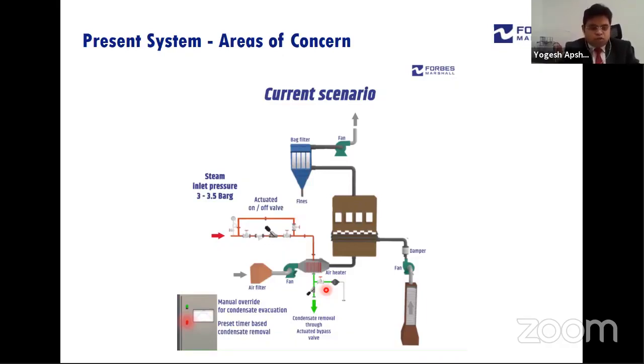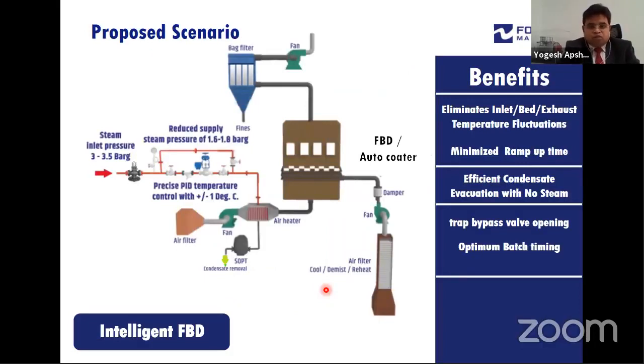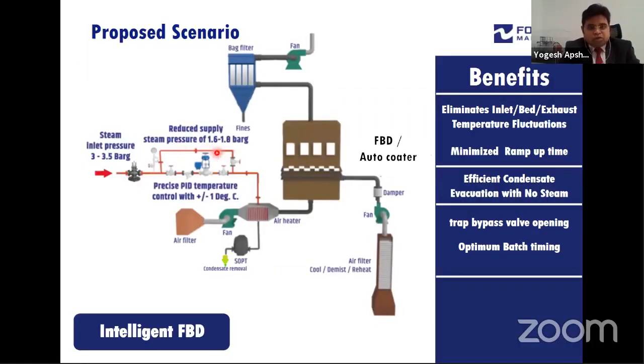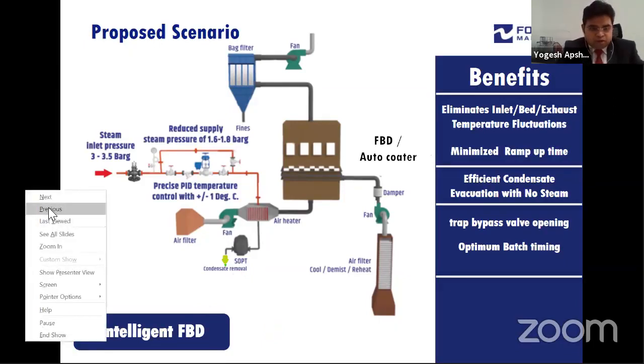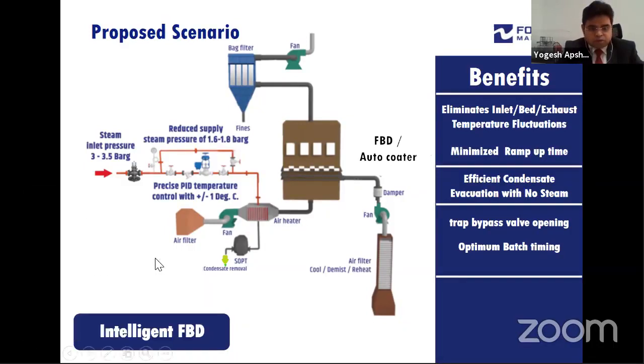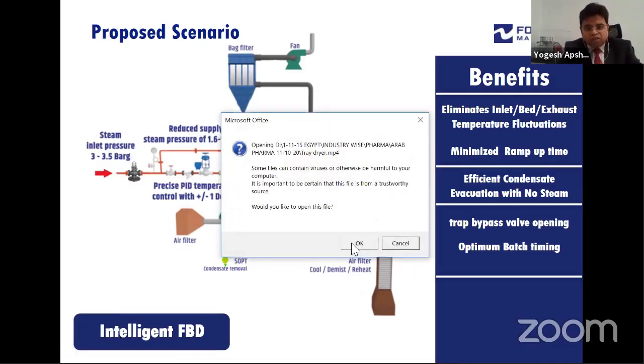So how do we get over this? This is what we have tried to do. An individual pressure reduction station for the fluidized bed dryers, maintaining a consistent pressure of 3 to 3.5 bar. Then a steam pressure of 1.6 to 1.8 bar at the inlet of the air heater battery, and condensate removal by steam operated pumping traps. I would just like to take you through a small animation which covers the problems and how we have overcome them.